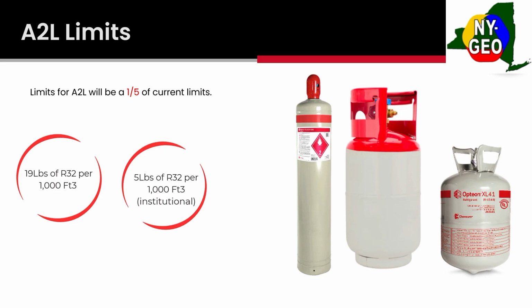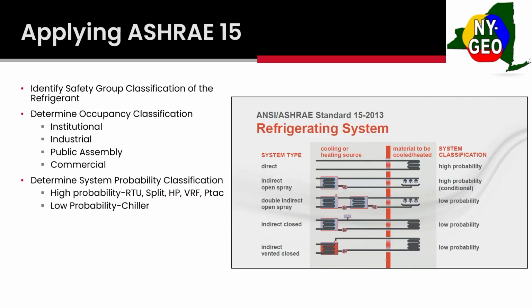It's important to know that the LFL is just looking at flammability. It's not looking at your respiratory health, anything like that. It's just looking at how much refrigerant is in the air or in a space that can safely disperse without being ignited. And ASHRAE 34, for all your different refrigerants, is going to give you this LFL value, whether it's 454B, R32, whatever it is. Pull out ASHRAE 34 and you'll get that information there. So we're going to use this in ASHRAE 15.